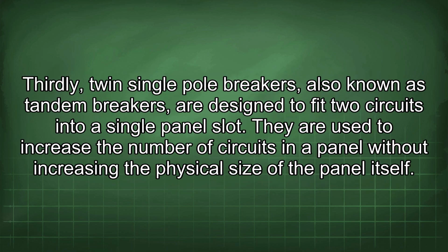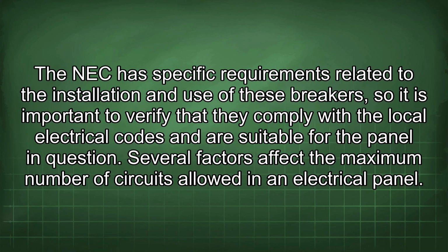Thirdly, twin single-pole breakers, also known as tandem breakers, are designed to fit 2 circuits into a single panel slot. They are used to increase the number of circuits in a panel without increasing the physical size of the panel itself. The NEC has specific requirements related to the installation and use of these breakers, so it is important to verify that they comply with the local electrical codes and are suitable for the panel in question.